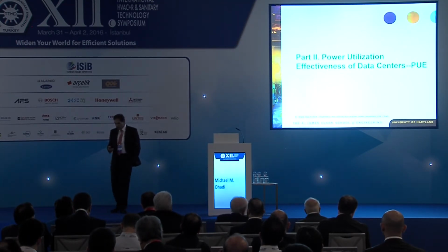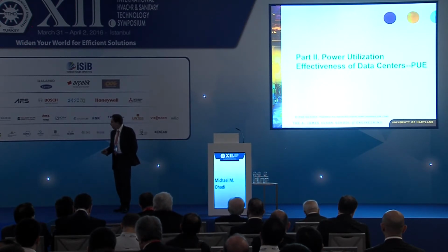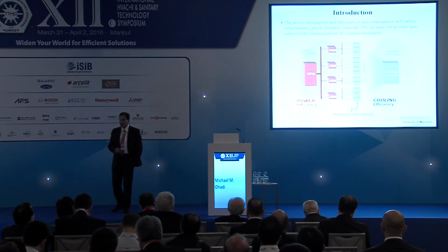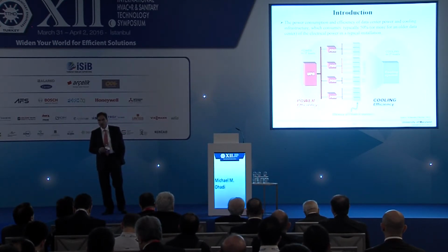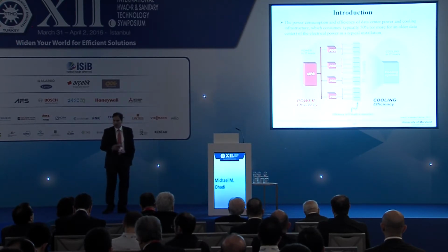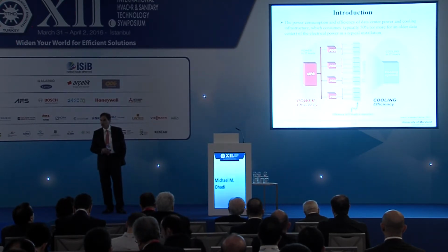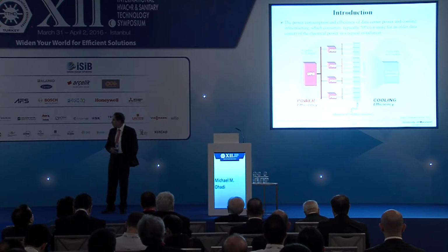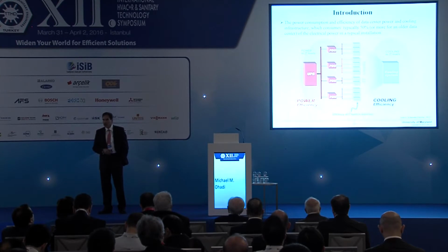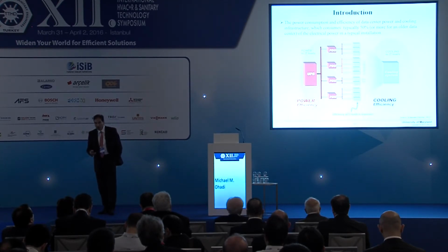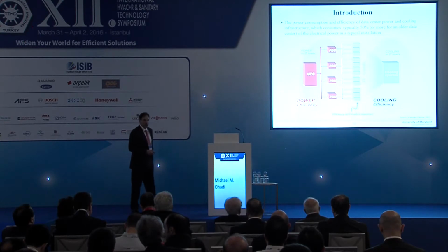So if I go back to a data center and look at it, I would have a situation like this. You bring the power to the data center through uninterruptible power supplies, then pass it through PDUs, power distribution units, basically to get any bad frequencies out of the power so that you have a regulated power into the servers. The servers then produce a lot of heat, and you have to use a source of cooling to keep this computer cool.